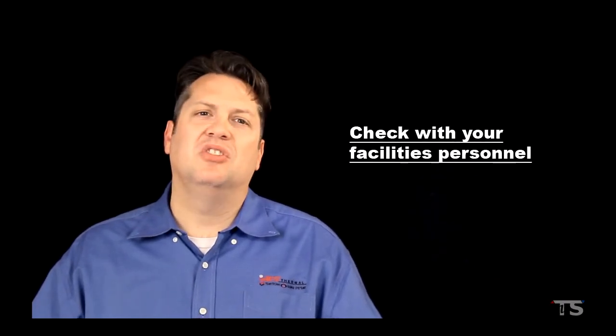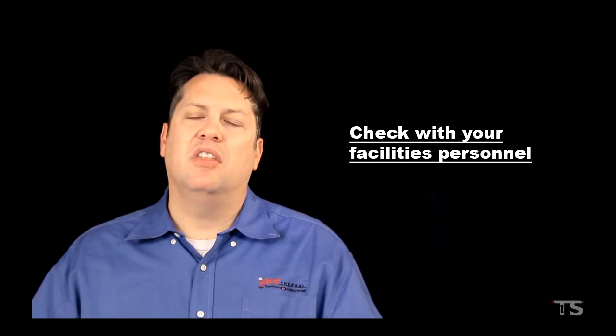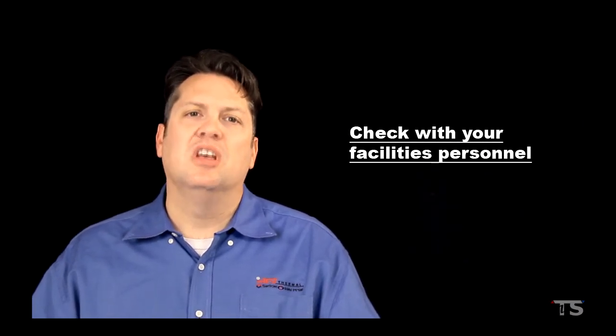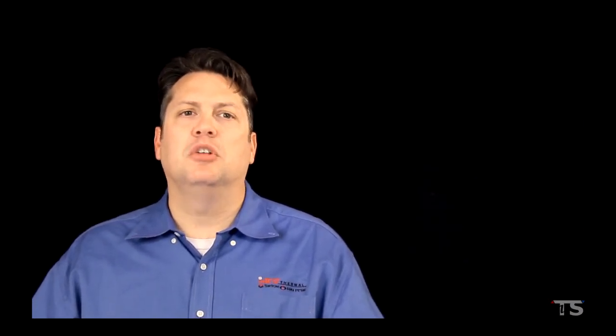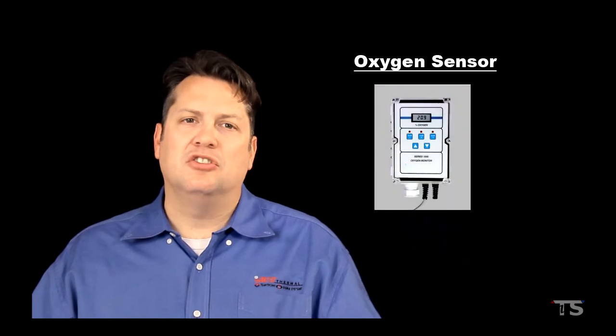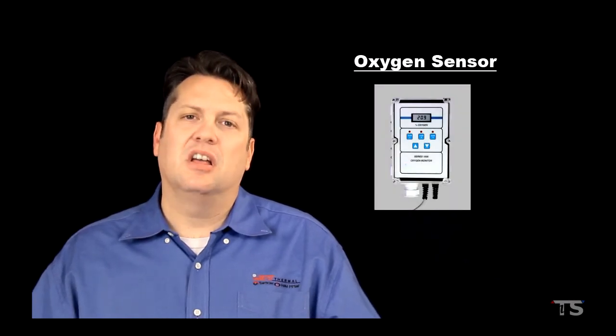You should check with your organization's facility personnel to verify that the area where your chamber operates is well vented. Generally large rooms and manufacturing floors are fine, but it's more likely to be an issue with smaller rooms and labs. Your facility personnel may determine that using an oxygen sensor is a good idea and good practice.